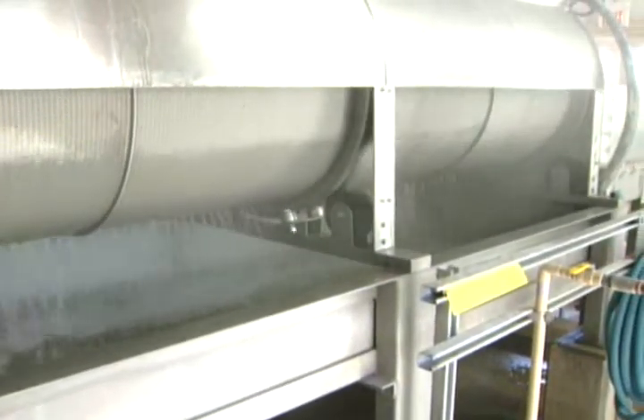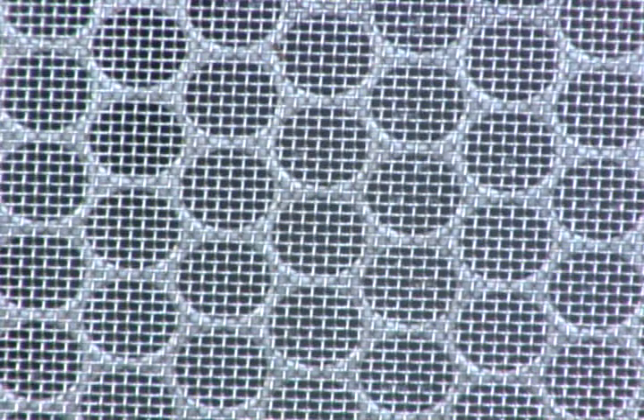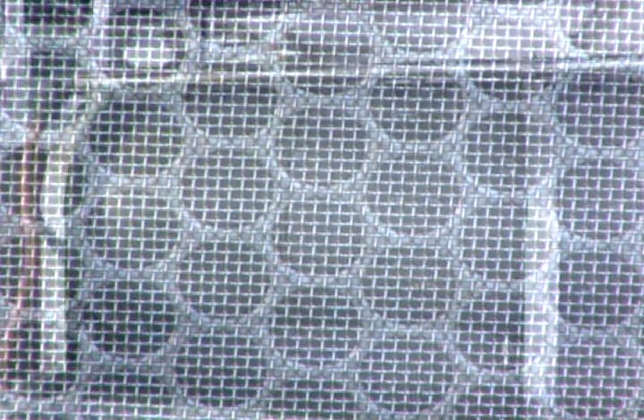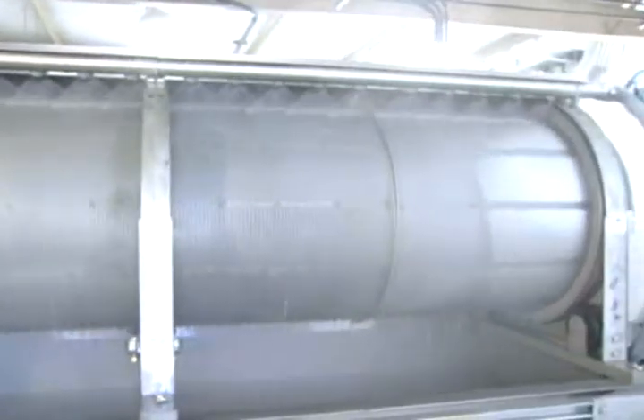In a typical configuration, the zones are covered with wire mesh, with finer openings used at the feed end and coarser openings used toward the discharge. This promotes maximum drainage as the sludge thickens. A spray header running the length of the drum keeps the screen clear, and the nozzles are cleaned with a simple turn of a wheel.